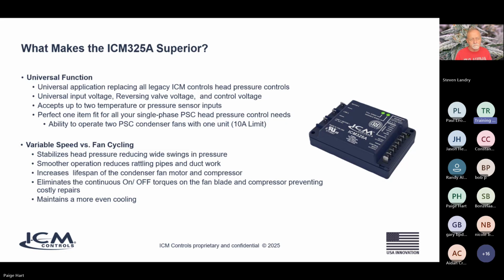Smoother operation reduces rattling of pipes and ductwork, preventing leaks. This increases the lifespan of the condenser, fan motor, and compressor, and eliminates a lot of those callbacks for refrigerant leaks and so forth. It also eliminates the constant on-off torques on the fan blade and compressor that prevent costly repairs. And you maintain an overall more even cooling, which is exactly what you're going to want in a lot of these applications.